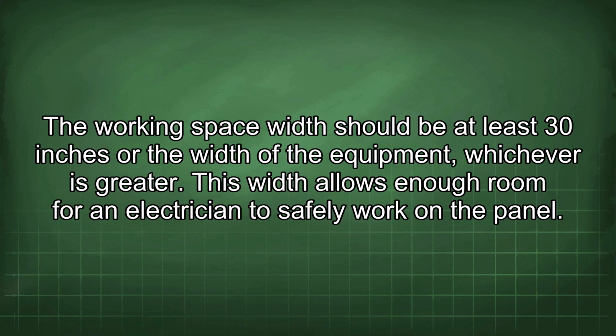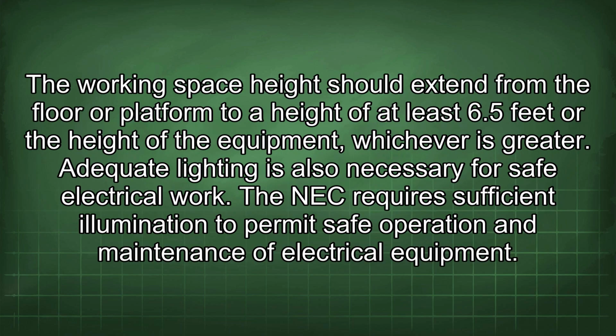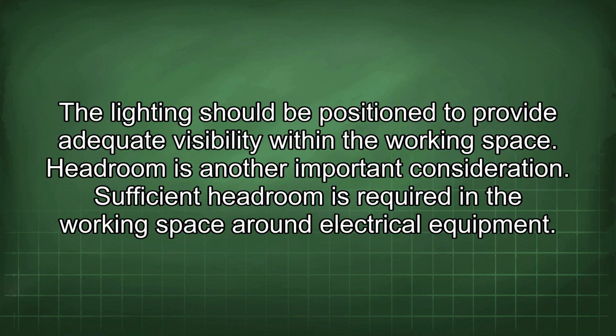The working space width should be at least 30 inches or the width of the equipment, whichever is greater. This width allows enough room for an electrician to safely work on the panel. The working space height should extend from the floor or platform to a height of at least 6.5 feet or the height of the equipment, whichever is greater. Adequate lighting is also necessary for safe electrical work. The NEC requires sufficient illumination to permit safe operation and maintenance of electrical equipment. The lighting should be positioned to provide adequate visibility within the working space.